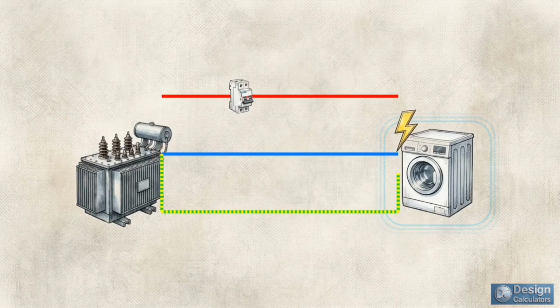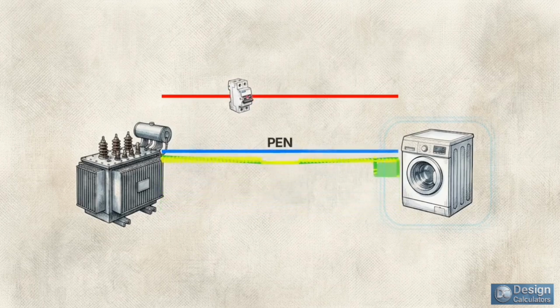When a live wire touches the casing in a TN setup, the current doesn't need to push through the dirt. The dedicated copper PE wire creates an incredibly low resistance loop. This pulls a massive current surge that instantly snaps the circuit breaker open.